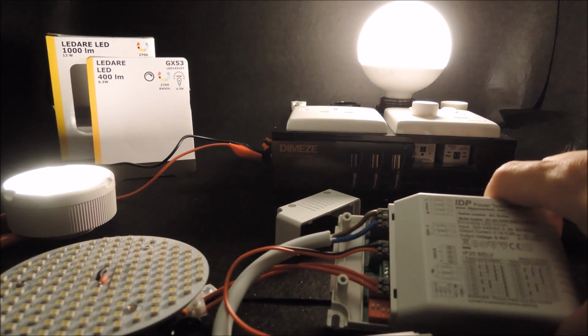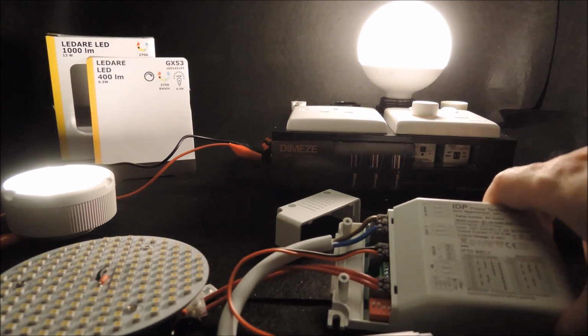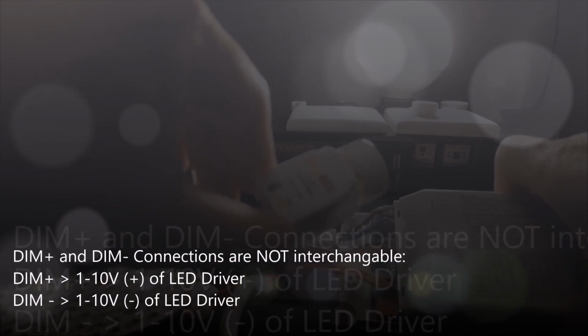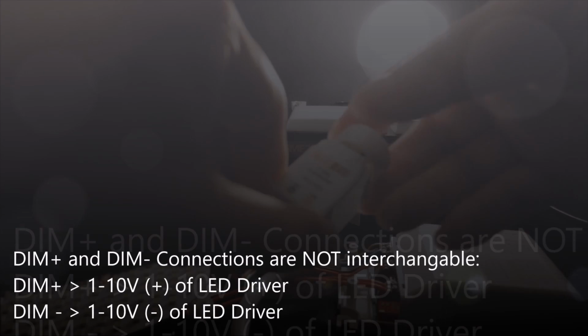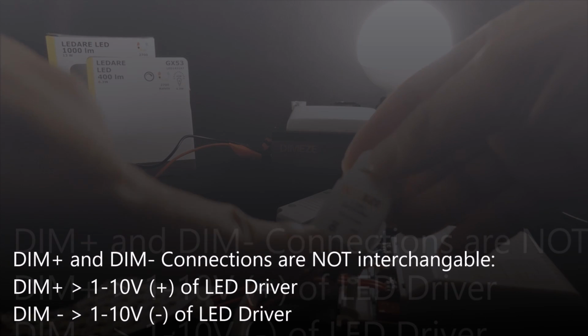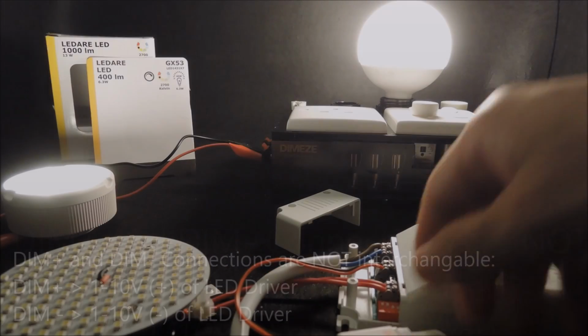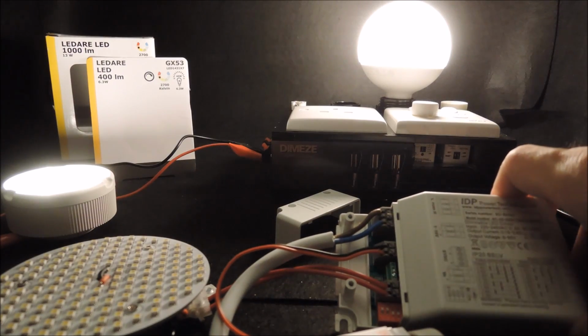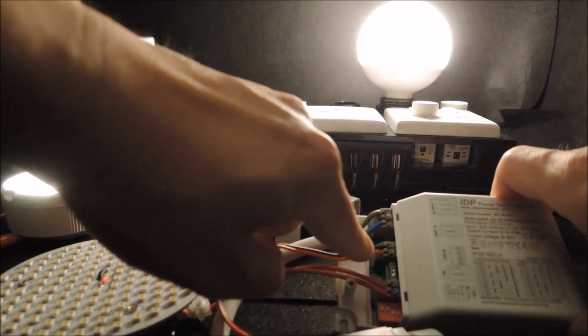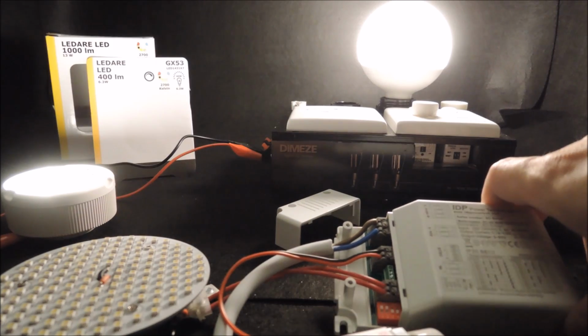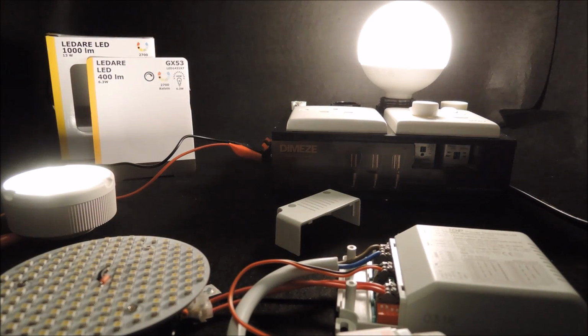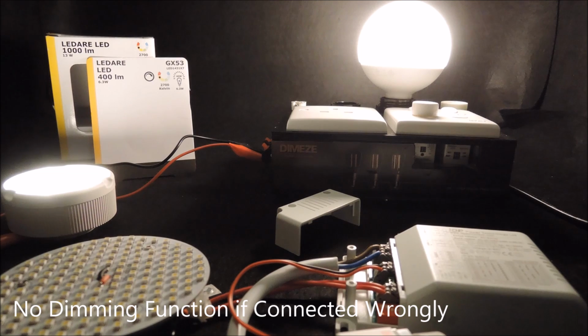And note for the 1 to 10 volt connection, the most often mistake people make is to connect the plus or minus terminals wrongly with the LED drivers. So do note the DIM plus and the DIM minus must be connected correctly to the driver. If connected in reverse, the lamp will still light up, but there's no dimming functions coming from the driver.